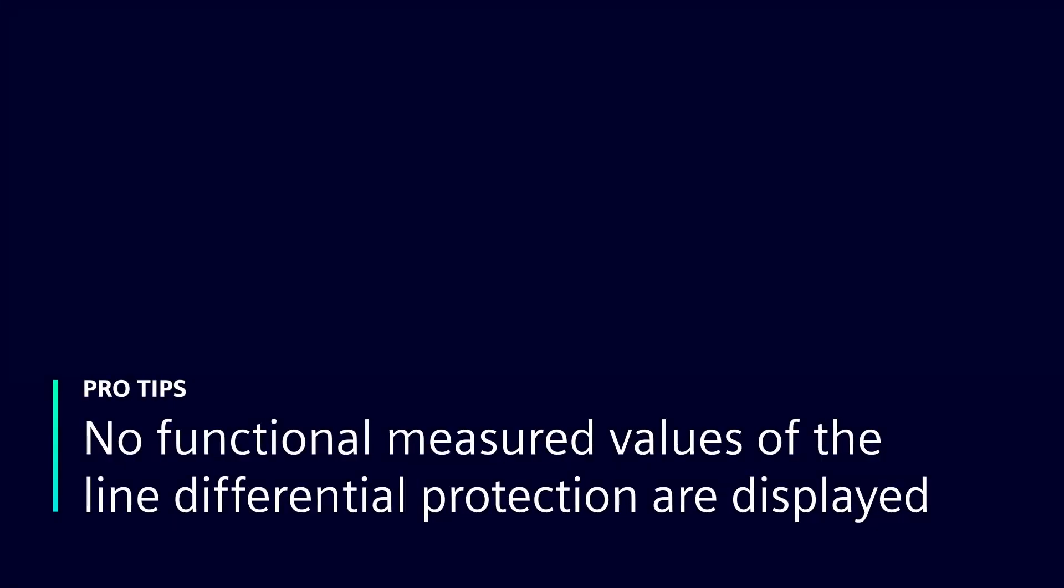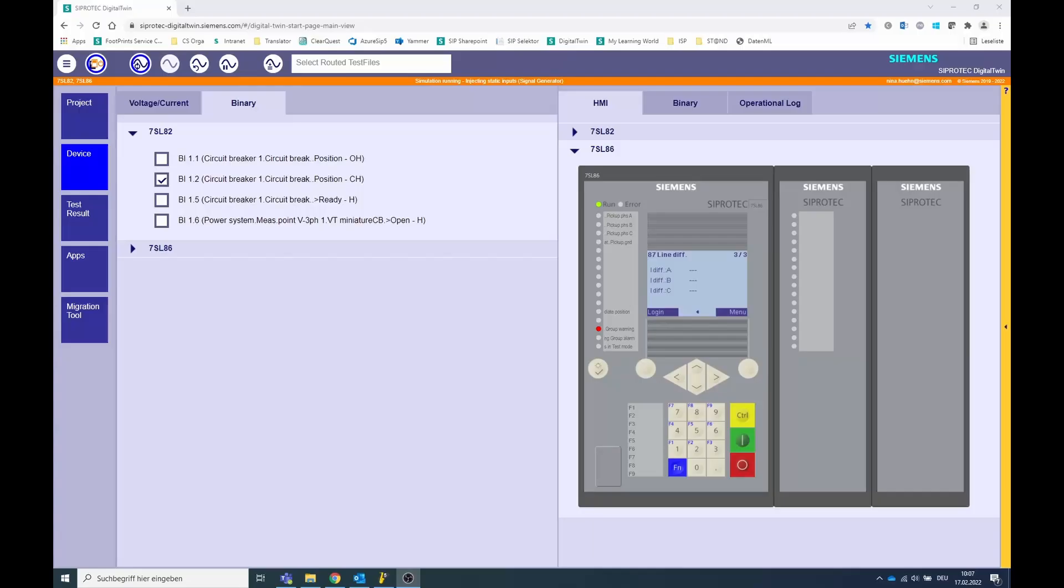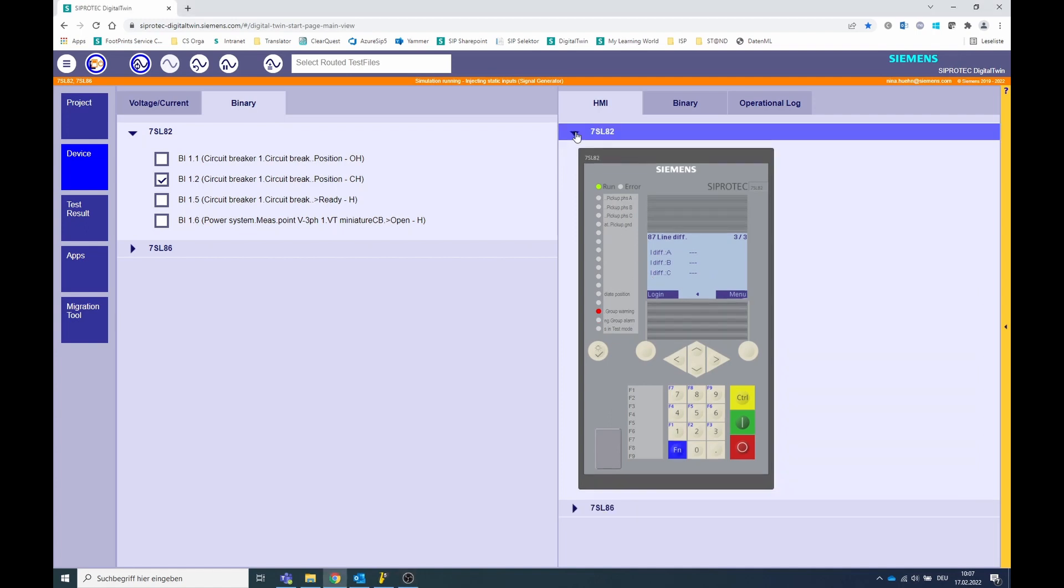If you find that no functional measured values of the line differential protection are displayed, the protection function is turned off or blocked. In this video we show you what causes this, using the example of a 7SL86 and a 7SL82 line protection device.